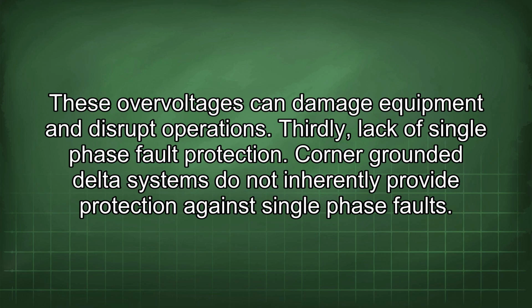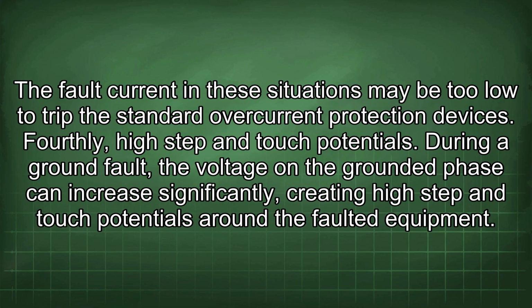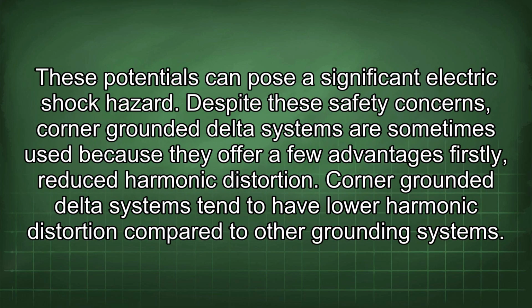Thirdly, lack of single-phase fault protection. Corner-grounded delta systems do not inherently provide protection against single-phase faults. Fault current in these situations may be too low to trip the standard overcurrent protection devices. Fourthly, high step and touch potentials. During a ground fault, the voltage in the grounded phase can increase significantly, creating high step and touch potentials around the faulted equipment. These potentials can pose a significant electric shock hazard.